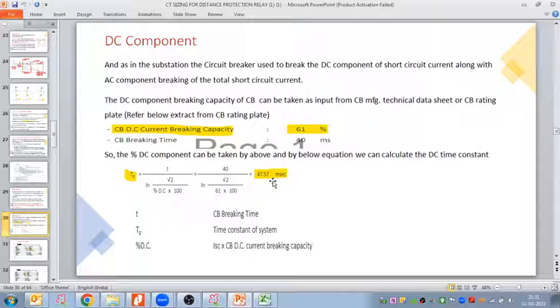Means the initial one cycle, how much time does it take? 20 millisecond for one cycle. So for the initial two or two and a half cycles, your fault current will have the DC component, and after two and a half cycles or after three cycles, the short circuit current will have only the AC component, because after 47.5 millisecond your DC component has decayed. This is the time required to decay the DC component. If you remember, we discussed these things during ETAP also, in the grid modeling, we discussed these calculations.